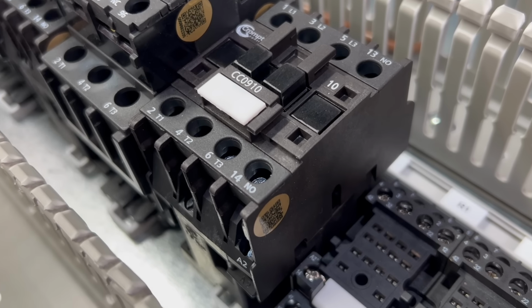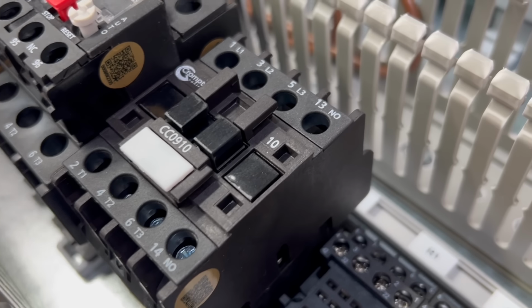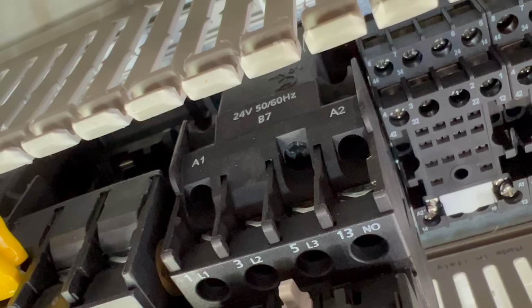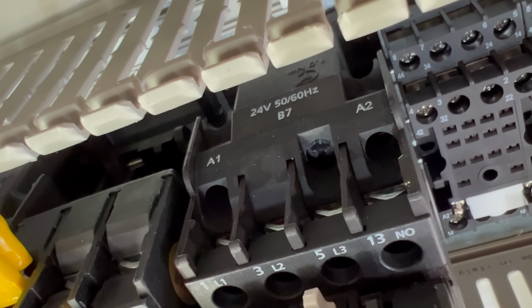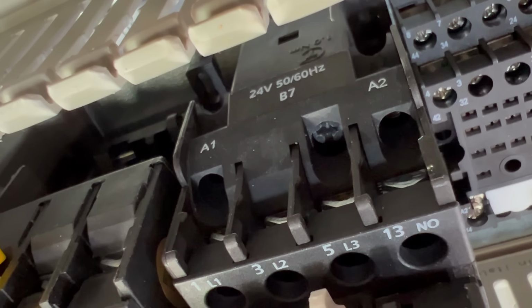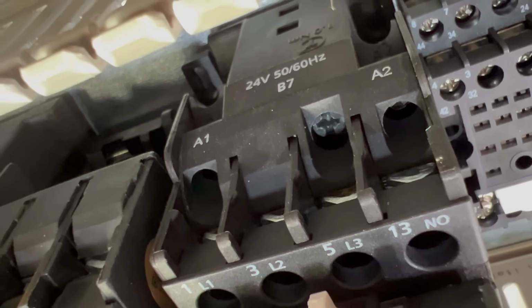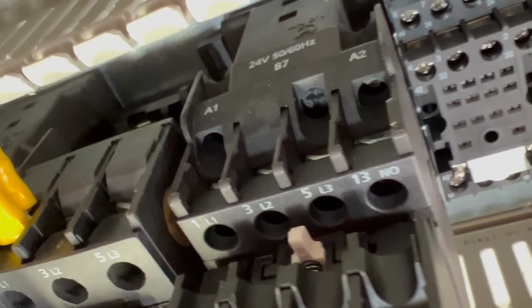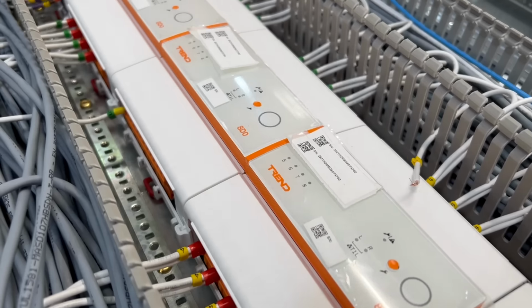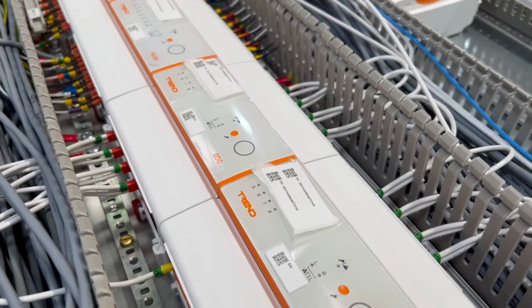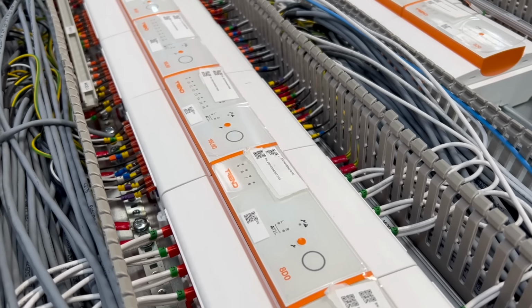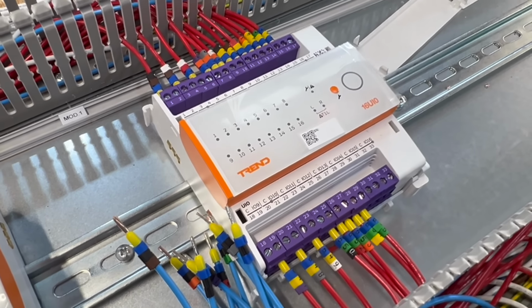So for a BMS panel, they might control large extraction units and other motors such as water pumps. They turn on and off via signals to these terminals marked A1 and A2. When they become live, they'll change their state and usually connect the supply through the contacts to whatever load they're feeding. I say usually because they can also disconnect the load when powered up, but this is a little rarer. Contactors have the advantage that circuits using large currents and voltages can be controlled by smaller devices with lower voltage and current ratings, like these direct digital controllers, or DDCs, that we'll get to in a moment.